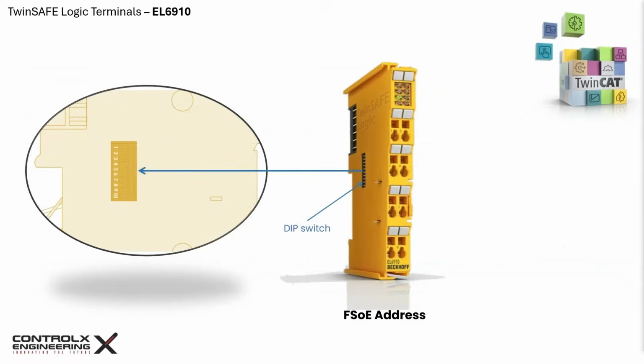These hardware set addresses are important because they prevent accidental mix-ups. Even if you move terminals around or download a new project, the safety controller can always verify that it's talking to the correct device. In other words, the DIP switches give each TwinSAFE terminal a fixed, tamper-resistant identity that's essential for safe communication.